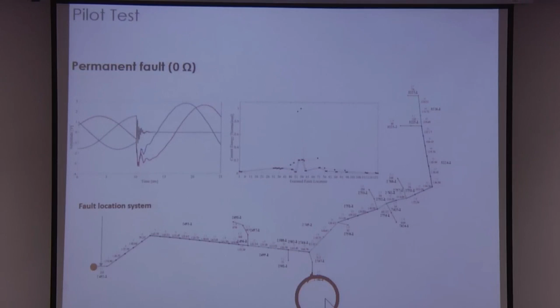So the utility helped us to create physical short circuits between conductor and ground, phase conductor and ground. They had circuit breakers to generate the fault. And this was the location where our system was installed, and this was the location of the fault, like 10, 12 kilometers far away. First we tried with the permanent fault, 0 impedance. This was the voltage we recorded. After that, the system automatically started the process, and this peak corresponds to the exact location of the fault. So we were able to distinguish and identify the location.